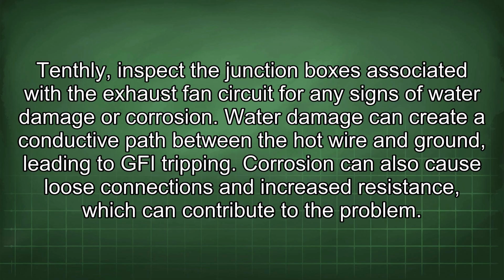Tenthly, inspect the junction boxes associated with the exhaust fan circuit for any signs of water damage or corrosion. Water damage can create a conductive path between the hot wire and ground, leading to GFI tripping. Corrosion can also cause loose connections and increased resistance, which can contribute to the problem.